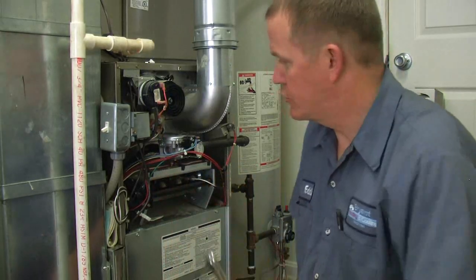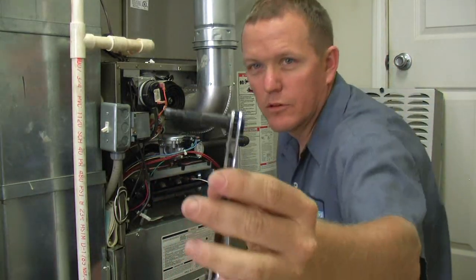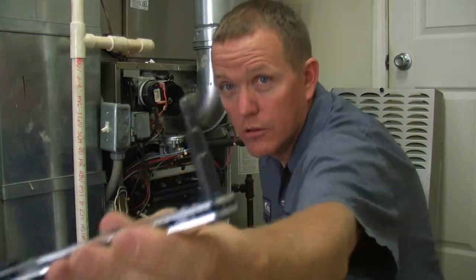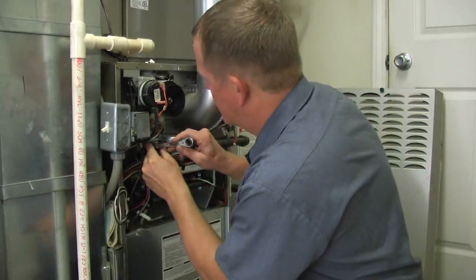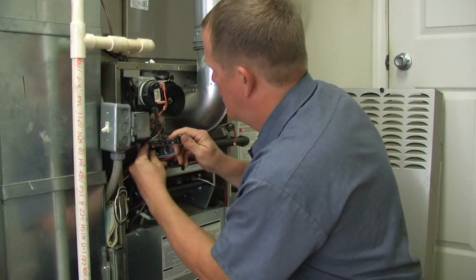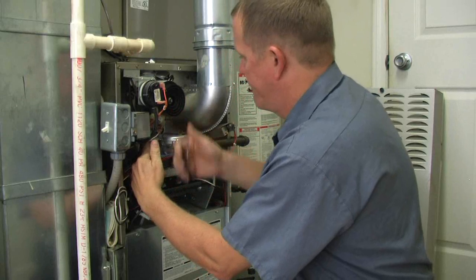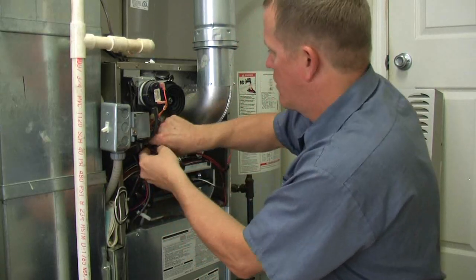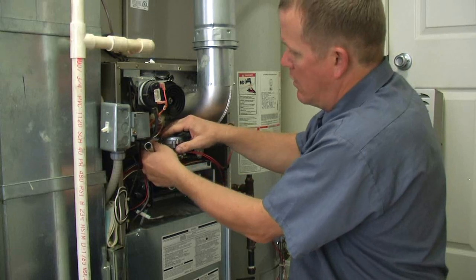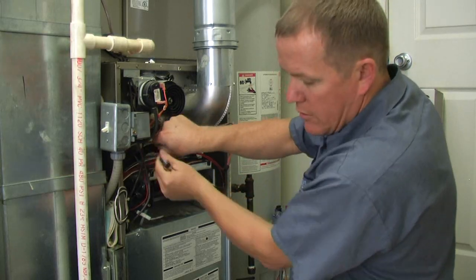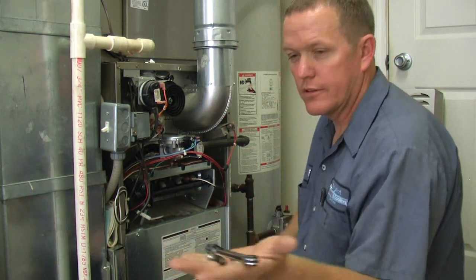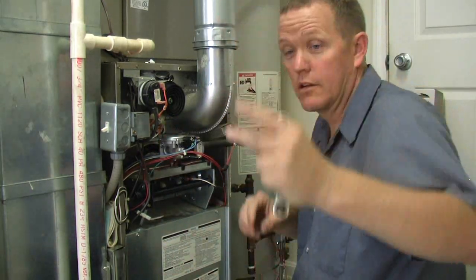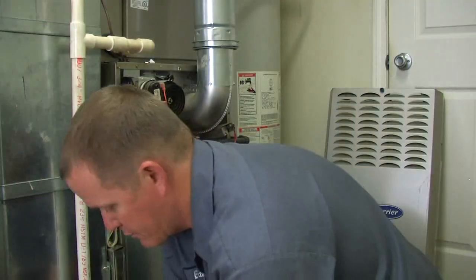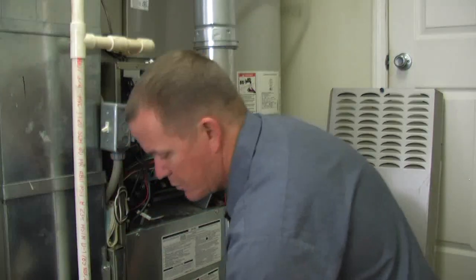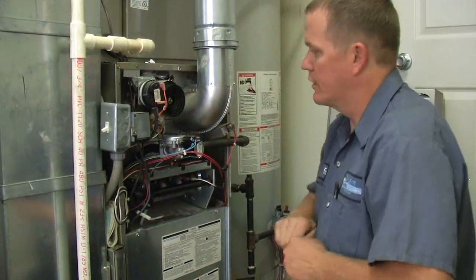Alright, so I'm going to use a speed wrench. It's the same one for opening up your service valves. It's the same wrench. Okay, so I'm going to take this off. Kind of set all these together because you do not want to forget to put this back in. And this is all it is. But you do not want to forget to put that back in. It would be a very bad day for a lot of people. So set all in with your tools. Make sure it's in plain sight so you won't forget.